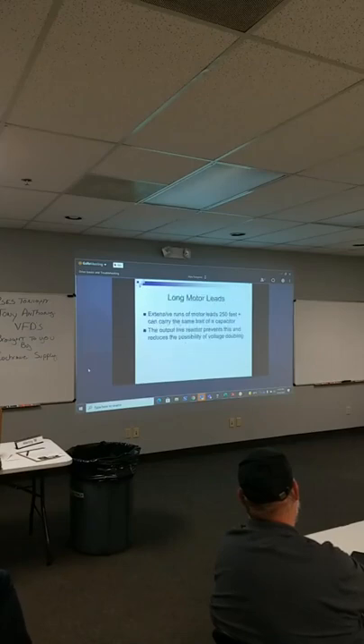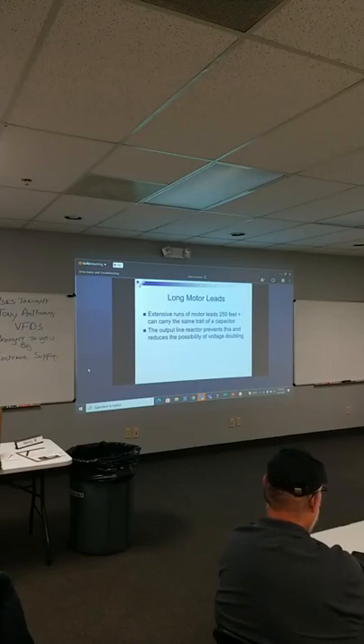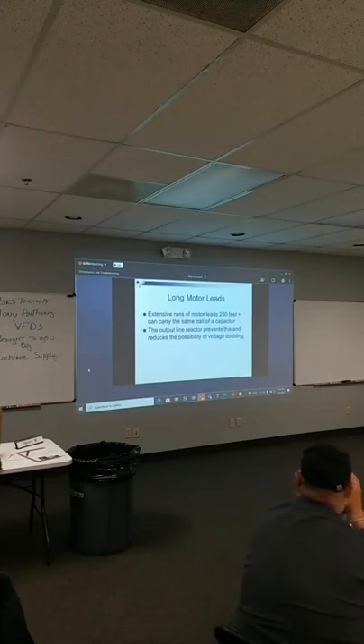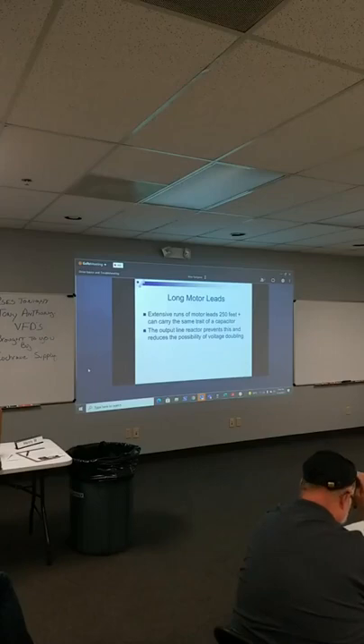And of course, we beat this horse already, the long motor leads. So this keeps saying 250. I've heard some manufacturers say that because all new equipment doesn't have as much metal in it as it used to. You get an old U-frame motor, those things were huge. Put a new motor in there now, and it's like a third the size. Because of the less metal in it, which could absorb some of that heat, we're getting more and more saying, hey, maybe come back to 200 or 150 feet before you start thinking about it.